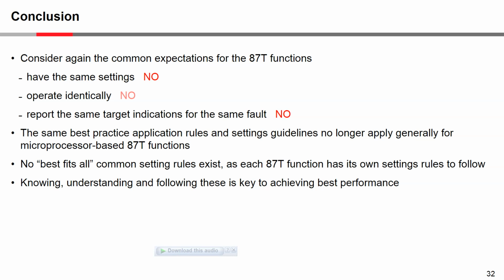And those are the things like, what is the transformation ratio? Because that adjusts, as I said through the presentation, even if you've got just balanced current flowing, the current flowing in and the current flowing out is going to have an unequal magnitude, which you won't have on a generator. The current flowing in and the current flowing out could have a different phase angle, which you won't have on a generator. The current on one side could see zero sequence and not on the other side for a transformer, which you wouldn't see on a generator. So, yeah, the generator 87G and the 87T do have to take care of a number of different things.